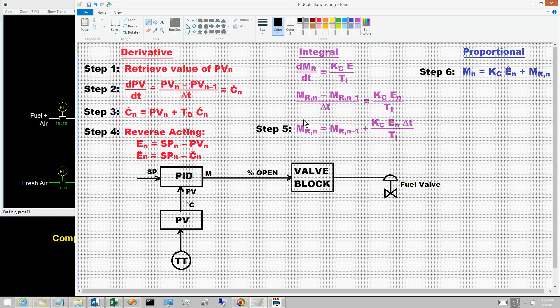Reset windup and reset windup protection are also deferred to a subsequent video. Under certain situations, the values computed for the controller output bias m sub r n can become very large, either positively or negatively — the result is known as reset windup. To prevent this from occurring, the computations must include logic known as reset windup protection.